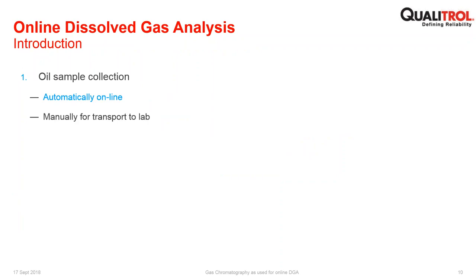So then, just an introduction to online dissolved gas analysis. The first thing you've got to do is collect a sample of the oil. There are two ways that this is traditionally done with online monitors. It is normally automatic online sampling, or alternatively, if you're sending a sample for laboratory GC analysis, it will be manual sampling, often into a glass syringe or some other type of sealed container.